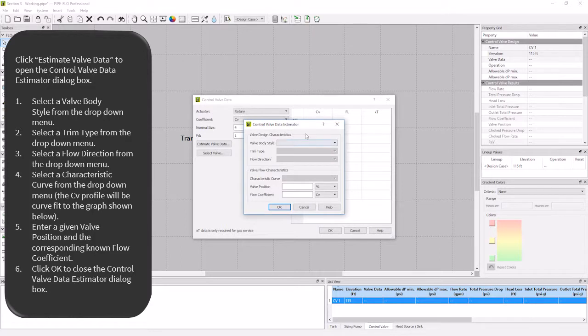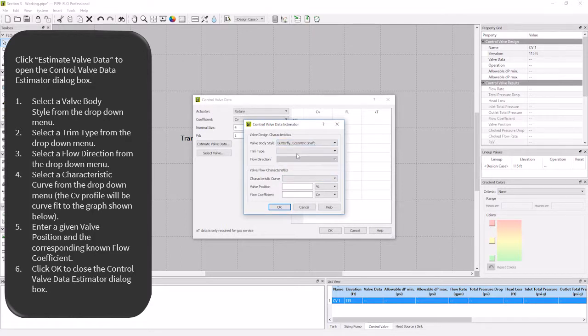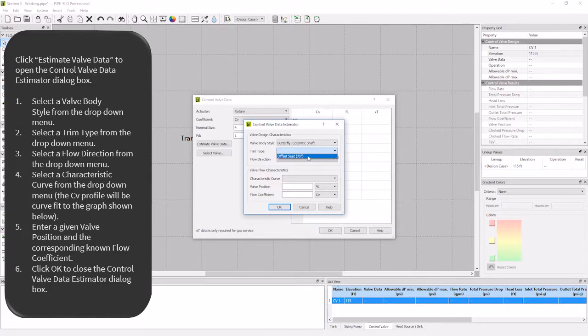My valve body style is butterfly eccentric shaft, with a trim type of offset seat 70 degrees. There are other options for other valve styles. My flow can go in either direction in the valve, so I will specify that as well.